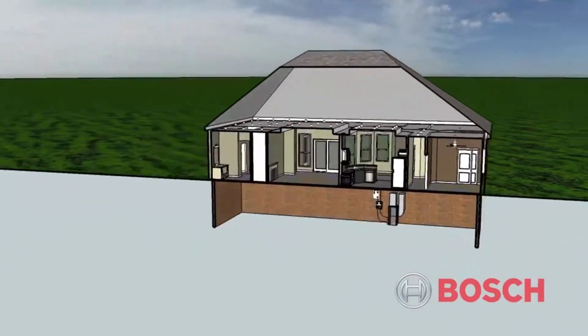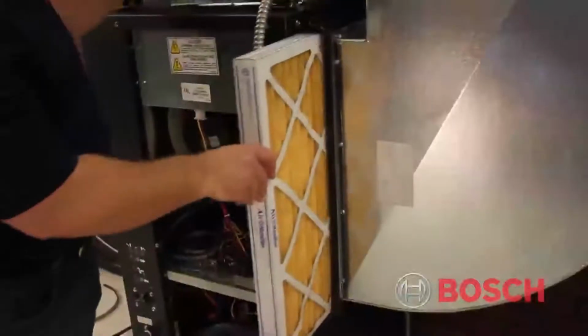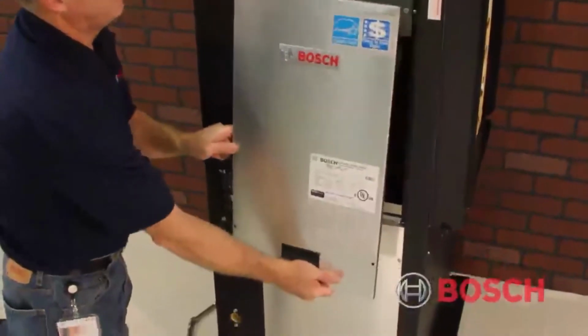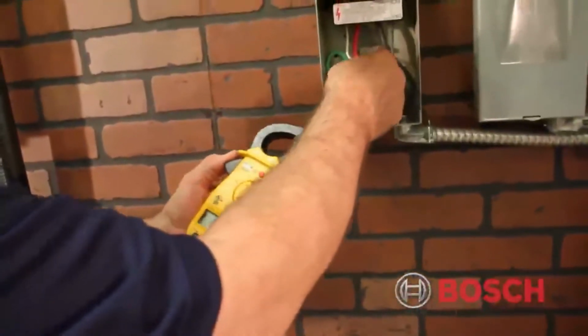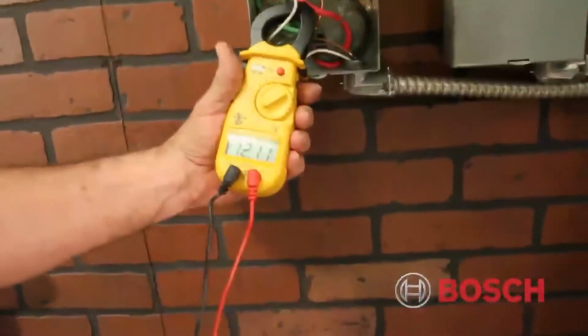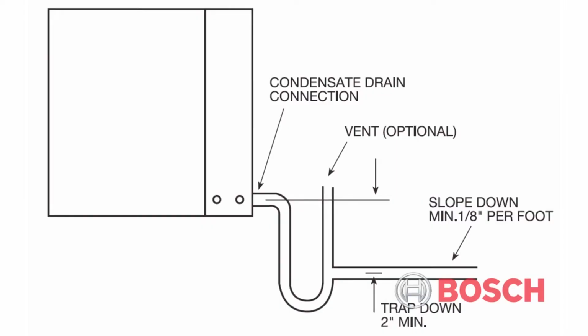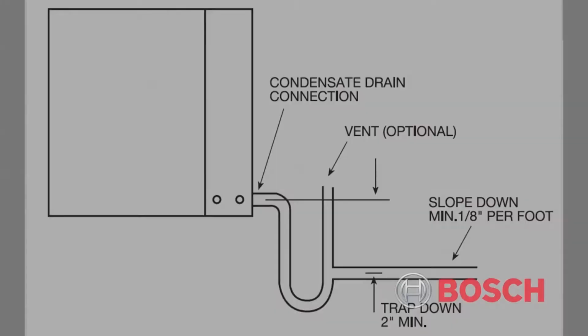Always locate the unit in an indoor area that allows easy removal of the filter and access panels and provides enough room for service personnel to perform maintenance or repair. On horizontal units, allow adequate room below the unit for a condensate drain trap and do not locate the unit above supply piping. Remember, these units are not approved for outdoor installation. Therefore, they must be installed inside the structure being conditioned. Never locate these units in areas that are subject to freezing.